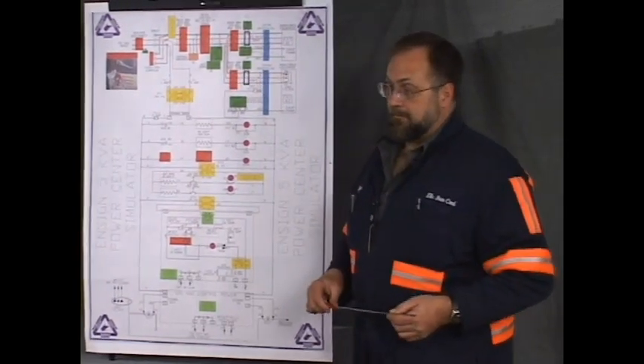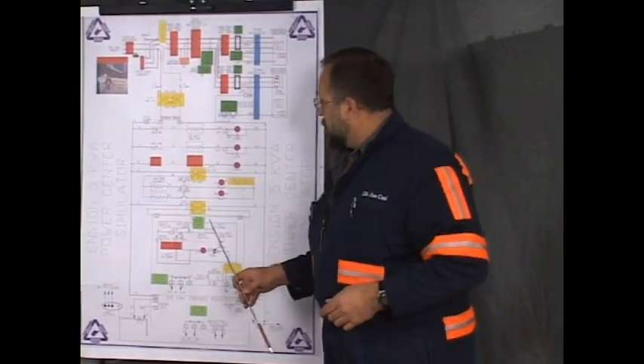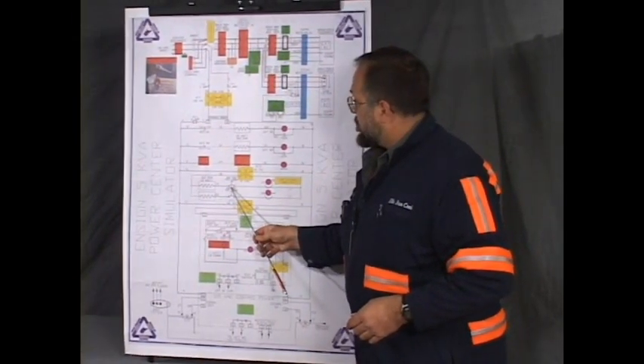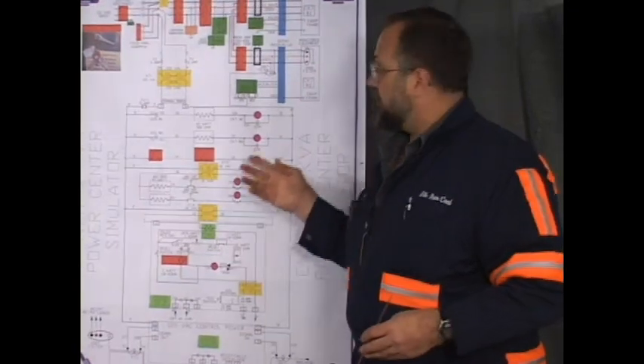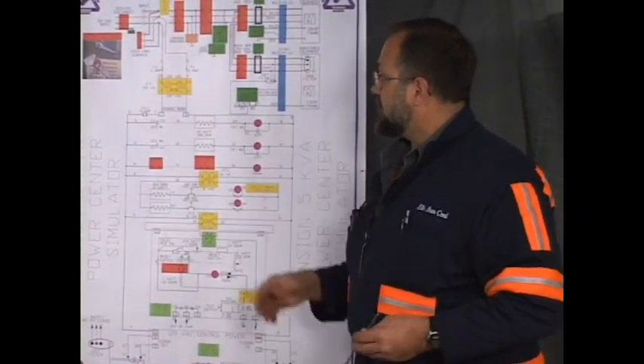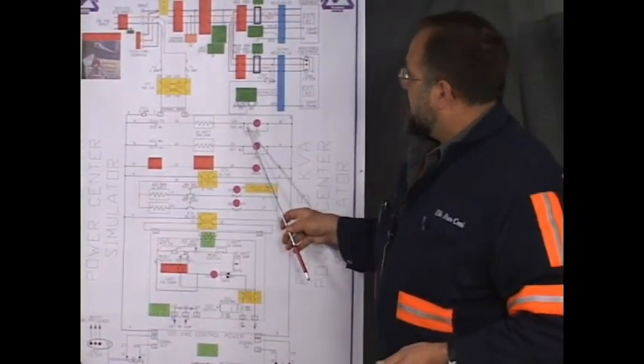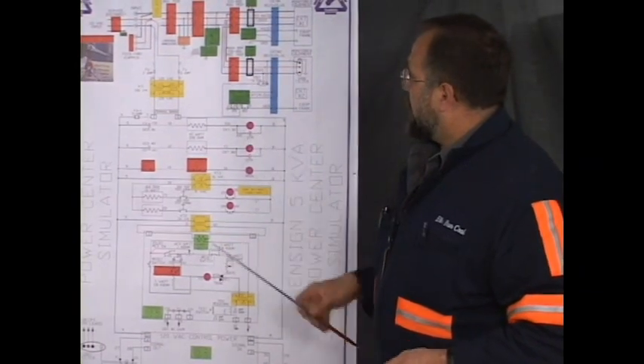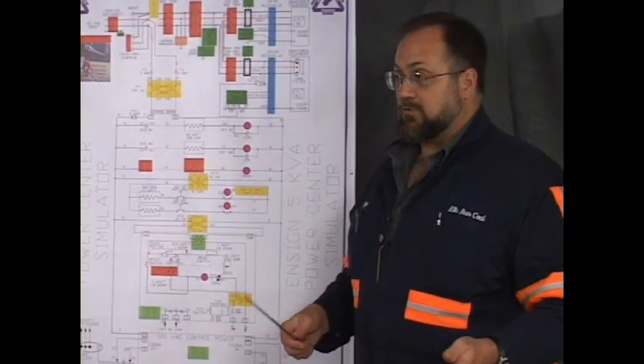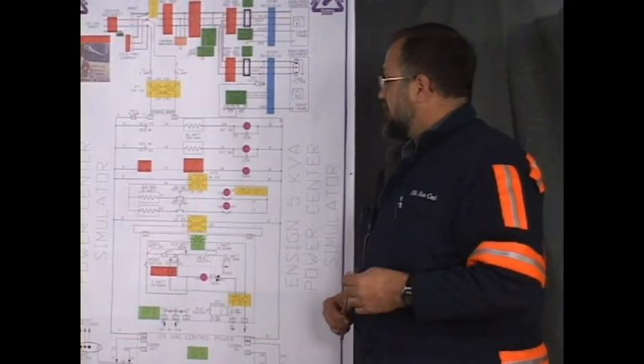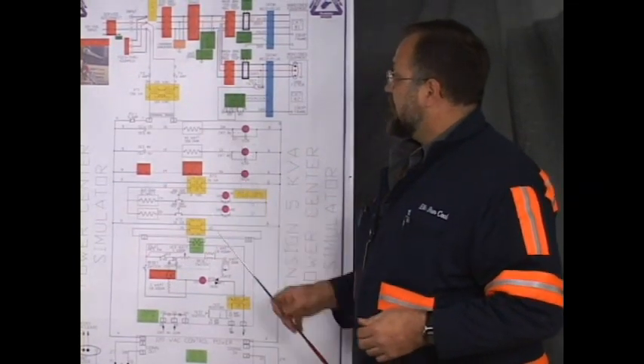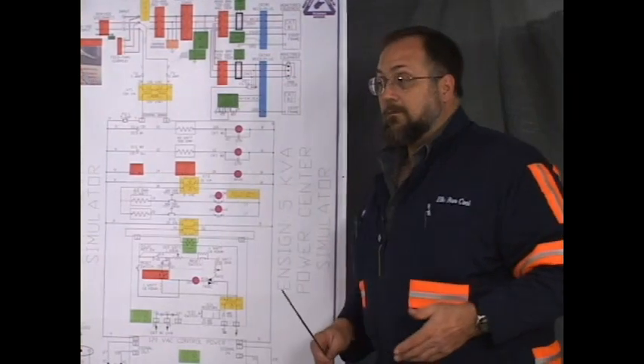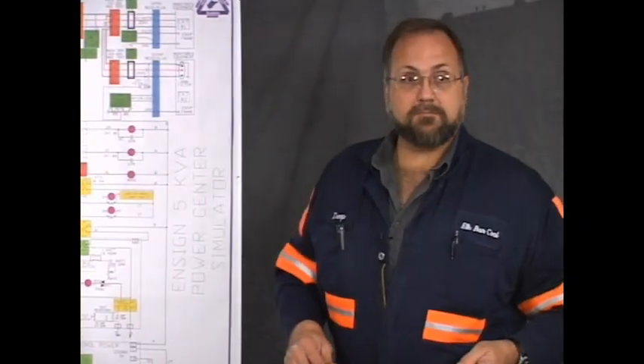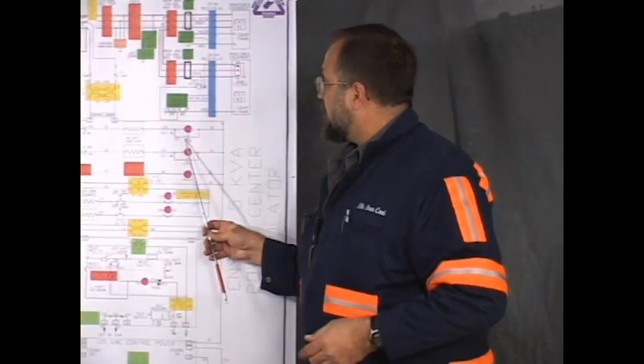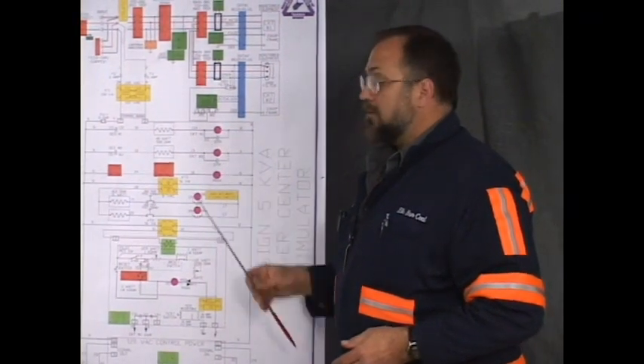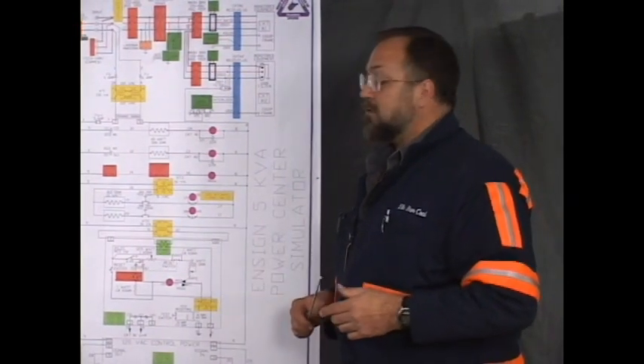Now we close them intentionally when you depress the ground trip test switch for circuit number 1 to check the function of this relay. You intentionally close those tips, and by closing the tips you provide a bypass for the UVR, and in essence you starve that UVR. The current will flow the path of least resistance, and rather than flow through the UVR and be converted to magnetism, it will take a direct path across these contact tips, and this UVR will lose its magnetism and cause the breaker to trip.